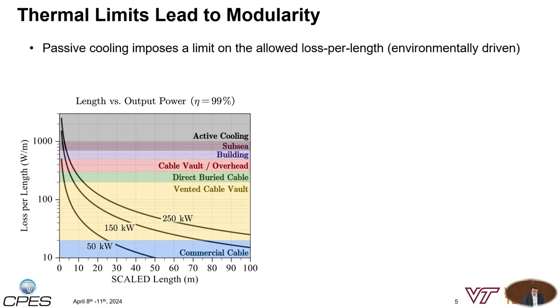Let's say I had a converter that was directly buried in the soil. For a direct buried environment, we can get somewhere between 200 and 300 watts per meter. So for a 250 kilowatt system, we need something like 15 meters of length. In another environment, say a vented cable vault, lower in the spectrum, that same 250 kilowatt converter might need to be over 100 meters long in order to evacuate the heat. That's an environmental limit. We can't really get around it.